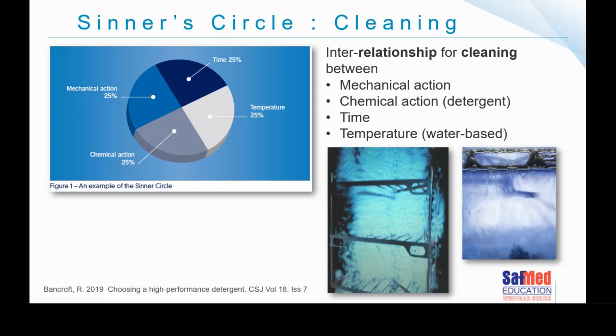Depending on the setup of your machine, these variables are arranged differently. You may have some chemistries that work at slightly higher temperatures, or chemistries that need a slightly lower temperature. You might need a stronger or lesser water force, or greater contact time. All of that is dependent on the setup of the actual device. Once the device has been validated and verified and it's good to go, you follow the instructions. You can't just change detergents or cycle times because you will truly affect the efficacy of that cleaning.